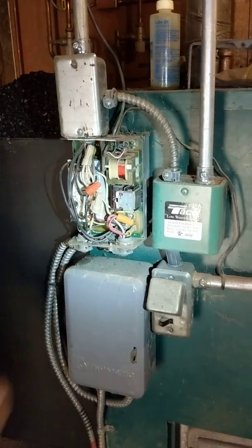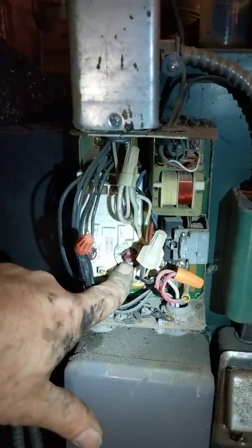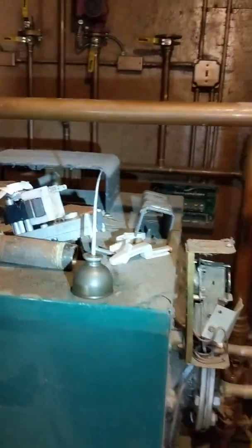Which is where we set that. This also controls the pump — as long as we're above whatever this lower number is set for, the pump will come on. Once we go below that, the pump goes off and lets the boiler recover. If we go up over 220, this here makes a set of contacts, turns on a pump, and cools the boiler off.